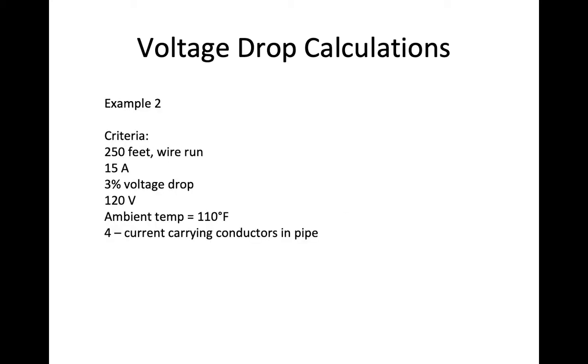Example 2. I have 250 feet of wire run, 15 amps again, 3% voltage drop, but now I decrease the voltage to 120 volts. We're going to run a temperature correction and a pipe fill correction with this in addition. So I'm going to figure out what is the size of conductor I need to get 15 amps from here to there. Then I'm going to apply conditions of use. So this might be on a rooftop or south side of a building that I'm running my pipe. 110 degrees Fahrenheit, 4 conductors in a pipe.